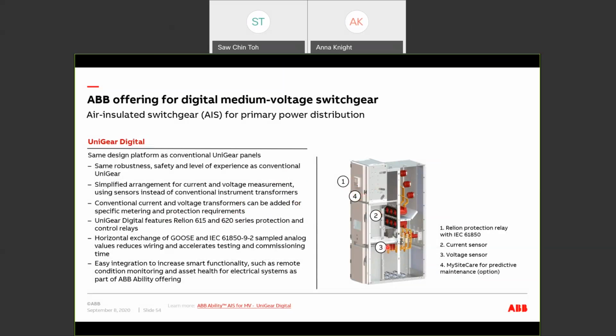By using current and voltage sensors and protection relays that rely on 615 or 620 relays with IEC 61850 and GOOSE messaging, it is actually an improved design with less wiring and better flexibility. Though the main focus is the sensors, we can still accommodate the conventional solution for specific applications, like revenue metering, where conventional CTs and VTs are required.